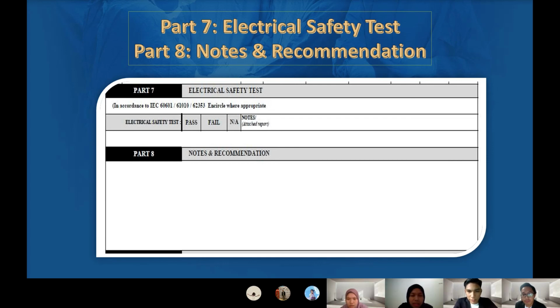Okay, I will explain about the electrical safety test and the notes and recommendations part. The electrical safety test helps to prevent hazards, and EST is important because it ensures the patient and the staff are safe while using the equipment. For the safety analyzer, we use the Fluke model. On the attachment part, the result of the test will be attached. For part 8, recommendations, the engineer will note down if the equipment has any damage or fault. For example, if the battery on the equipment is damaged, the engineer will note down that the battery will be replaced or changed.